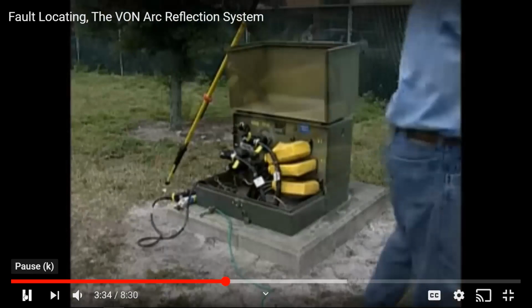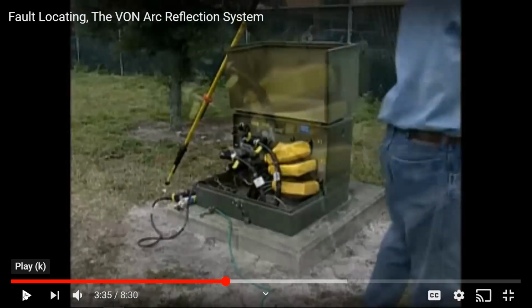Okay, did you hear that safety note? That'll be a test question right there. The green case ground to the VON has to be uncoiled completely, even if you have to stretch it out over the ground. Why is that? It will act like a winding. That's right.